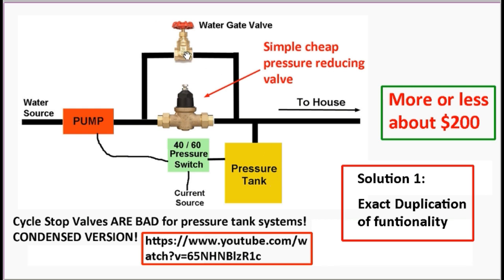But this gives you the option of adjusting this valve to as high a value as possible and avoid the cycling, which will take some experimentation. But once you have experimented correctly, you can set this valve to that value and forget about it, and you will get no cycling on the long runs, and the pressure tank will fill up faster than it would with a cycle stop valve because you've set the dribble rate, the bypass rate, to your custom setting for your custom system.